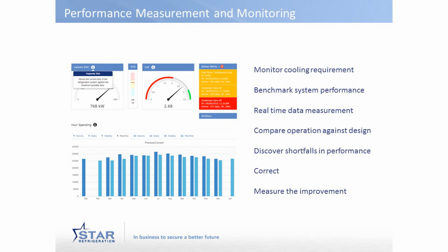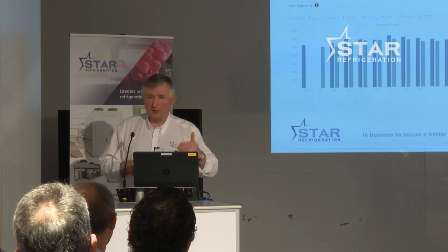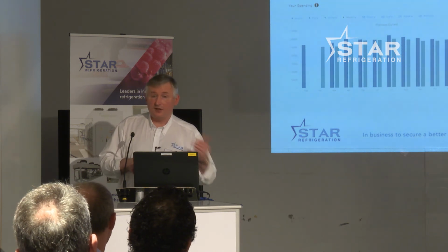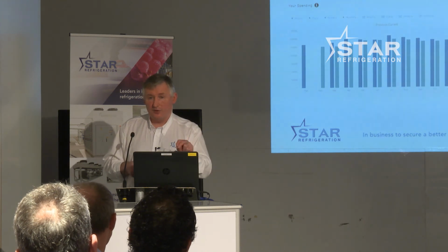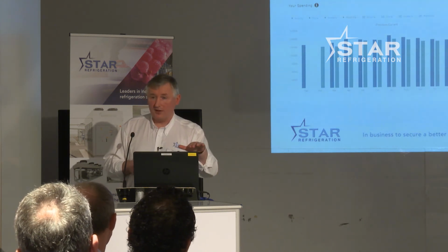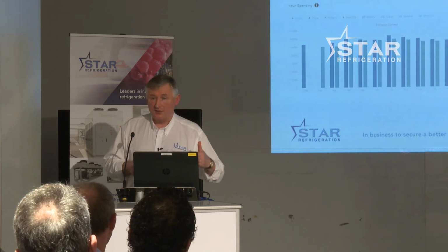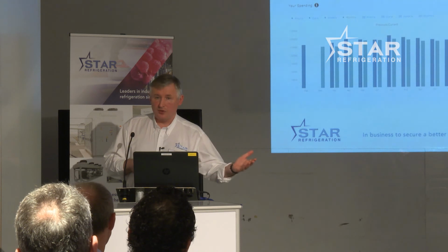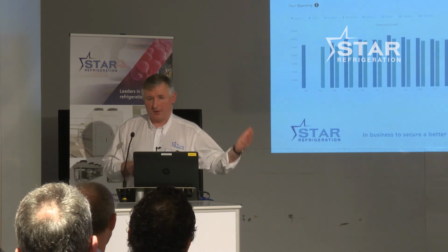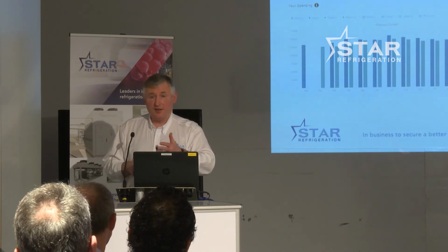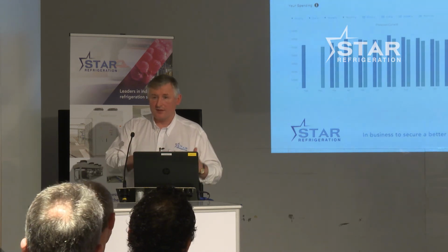So it really is a very, very powerful tool. What it's doing is taking readings of operating pressures, temperatures, ambient temperature, product throughput, whatever you want to measure can be fed in. The data is sent off-site and is then analysed with various algorithms that STAR have developed to look at the optimal performance, and then it turns that back into money and says, if you were able to do this, it looks like your plant's not operating ideally. If you're able to do this, then it will save you this much money, and making that change might cost you so much. So it might cost you £1,000 to make the change, but it'll save you £2,000 a year. That's the way that Ethos presents the information back.